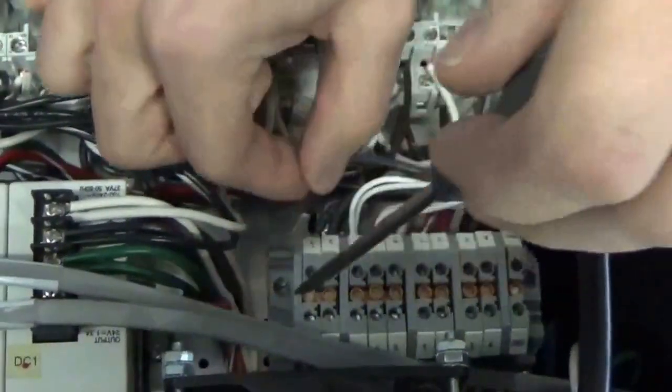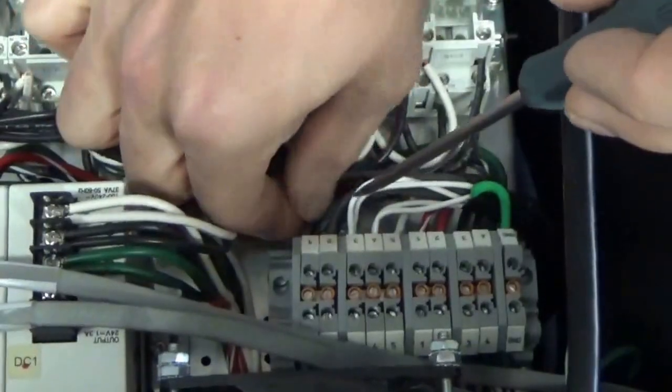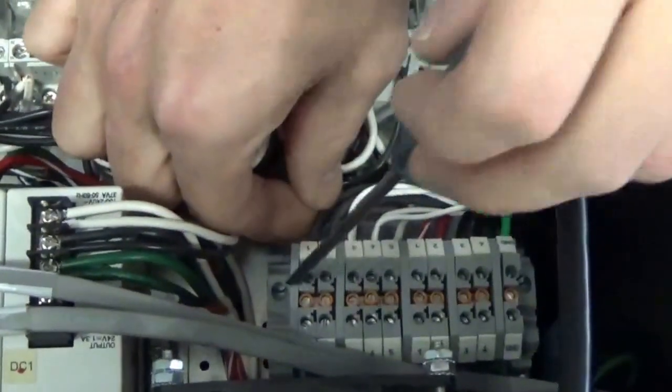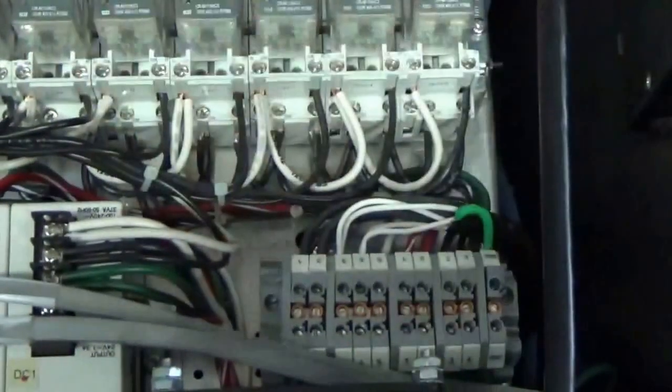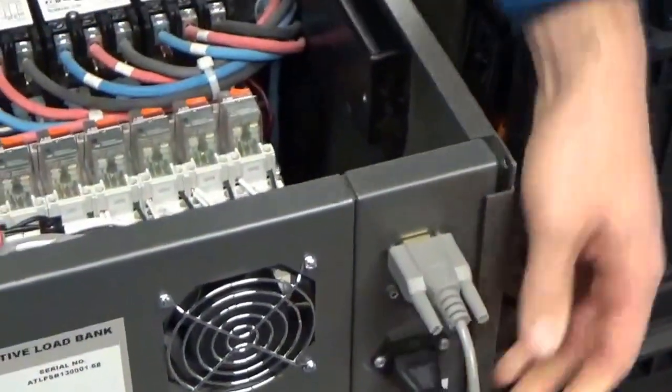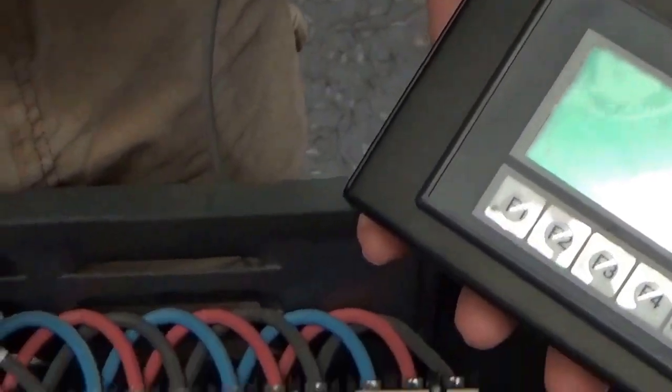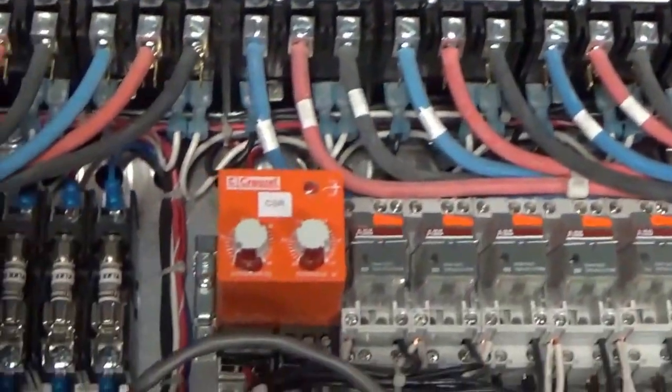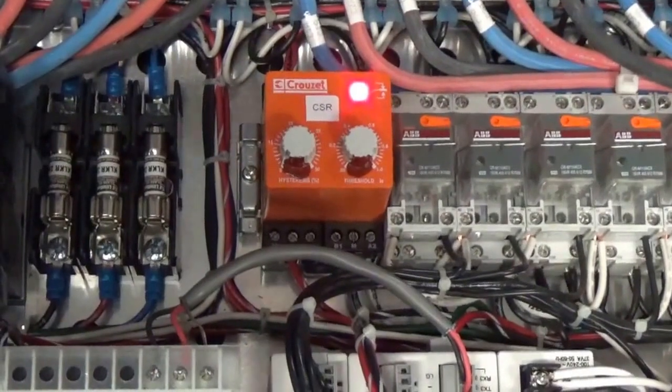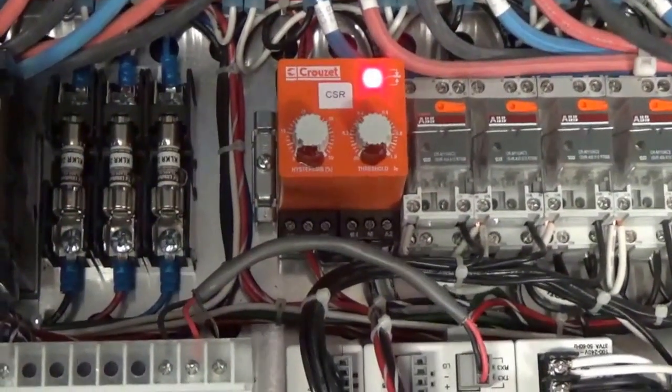We're going to plug our load bank back in. We're going to turn on control power. There we have it. Light's on. I can go to my air screen on the HMI. Cooling fans are okay.